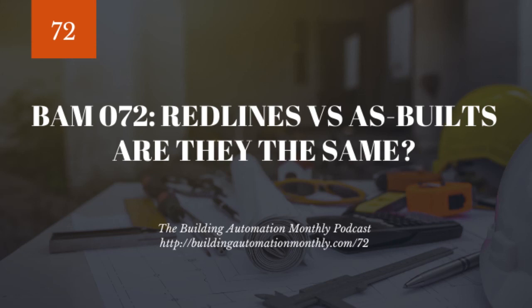because of this, maybe the controls tech does not have the latest change because construction communications are not necessarily the best. And by the way, this is why you should be at job meetings. This is why you should go to the job site meetings. Because if you're not aware that the mechanical plans have changed and they haven't been sent out to you, you could be entering min and max CFMs or programming boxes or all sorts of things, and it be completely wrong. And you're just wasting time. You're messing stuff up because it's not properly designed. So you really got to keep pace with these kinds of things.